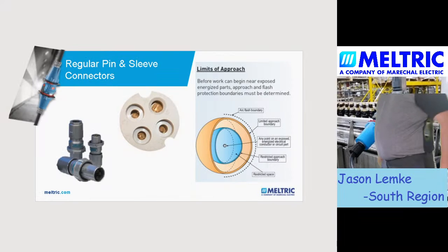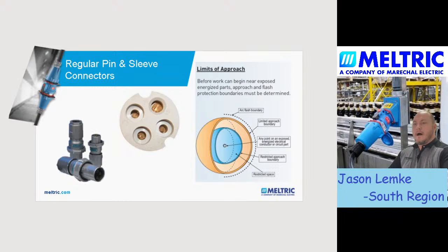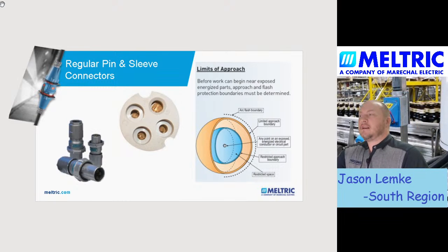So let's go back a little bit to that presentation, and we'll talk a little more about the dead front shutter side of things. This is where it's super important to have a dead front shutter, because when you remove a plug from an energized receptacle, you will have exposure to conductors. When you are exposed to a conductor that has not been verified zero energy or de-energized, then you have this limited approach boundary, and that triggers all of those electrical safe work procedures that you have in place through NFPA 70E. You have to get a qualified person to do that.